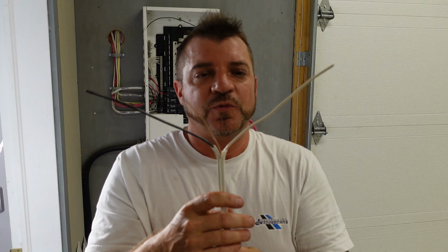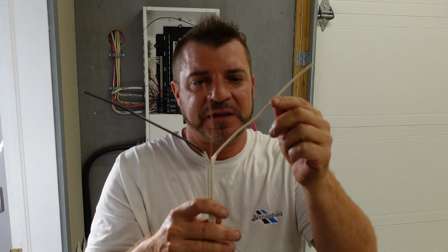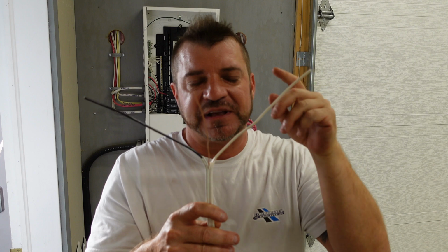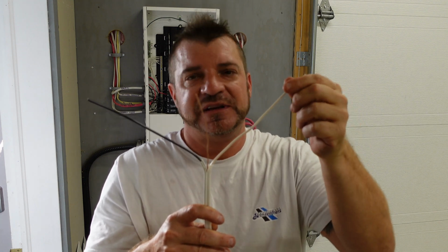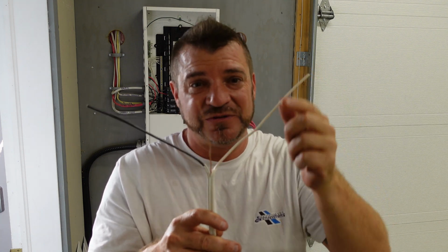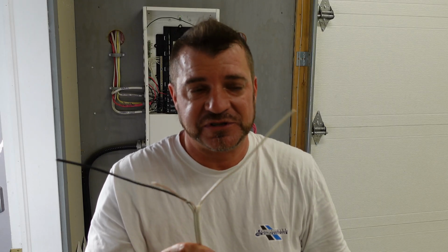So with the identified conductor, this is where the electricity flows, and this is where it gets very confusing, because even though this is not technically a neutral, we'll refer to it as neutral on the job site or in the trade, or slang term or whatever you want to call it, and that's where people get confused. But us as electricians know that the 3 wire or 4 wire or however many wire it is always has one unbalanced neutral. So in a 4 wire, we'll have the white, red, black, blue. The white is always considered to be the neutral.